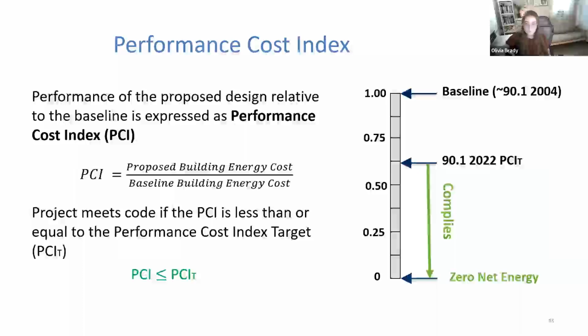Okay, so as I just mentioned, the Appendix G baseline is approximately aligned with stringency requirements in 90.1-2004. The 2004 efficiency levels are obviously significantly less stringent than what's required prescriptively by 90.1-2022. So we can't establish compliance just by comparing the proposed design energy costs to the baseline energy cost. In fact, the proposed design energy costs must be less than the baseline by a set margin.